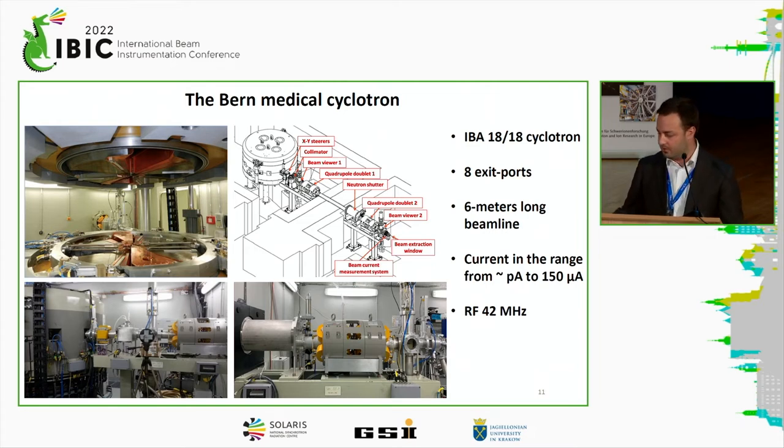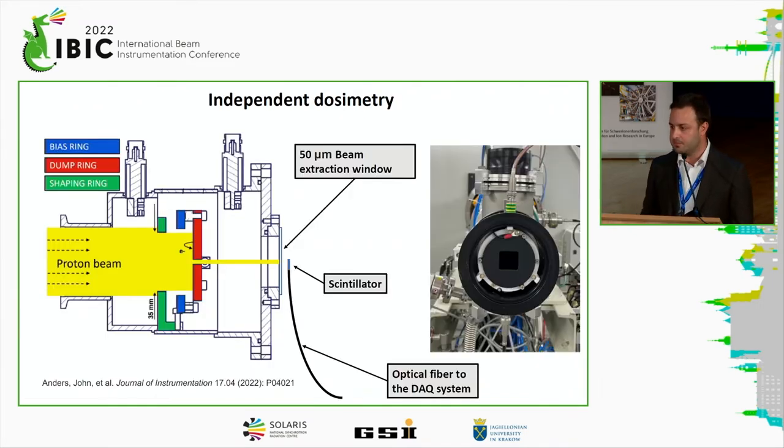Now, one of the advantages that we realized, let's say, by chance, is that when we keep the ion source very low, because this cyclotron is designed for very high current, for production, but when we keep it low, basically we are in the range of FLASH at 18 MeV, which of course is not a medical energy, but still it's good for testing new detectors and instrumentation.